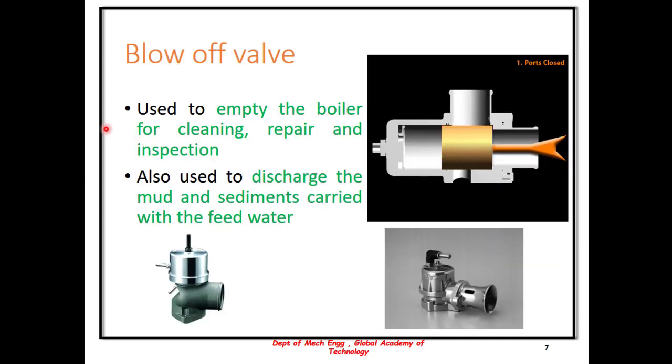The blow off valve is basically a valve used to empty the boiler whenever there is cleaning, repair or inspection needed to be carried out. It is also used to discharge the mud and the sediments which are carried with the feed water. When the feed water is given to the boiler, it is already cleared and filtered out. Nevertheless, when the water enters the boiler, there is still some amount of sediments left. To remove these sediments, the blow off valve is used.